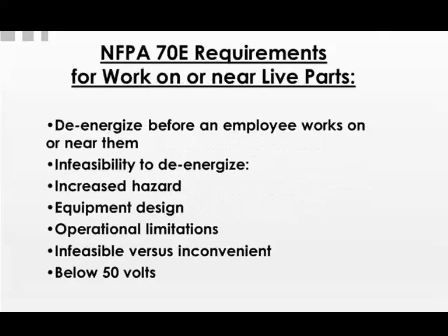All right. NFPA requirements for work on or near live electric parts. De-energize completely before an employee works on them, lockout, tagout. If it's infeasible to de-energize, you've got an increased hazard, obviously. You have to look at equipment design and operational limitations. But there is a big difference between infeasible versus inconvenient. If something's inconvenient, it has to be de-energized. The standard doesn't account for that. If it's infeasible, meaning it has to be energized because of, let's say, troubleshooting or whatever the case may be, then it trips the requirements for working on live electric parts, or if it's below 50 volts.